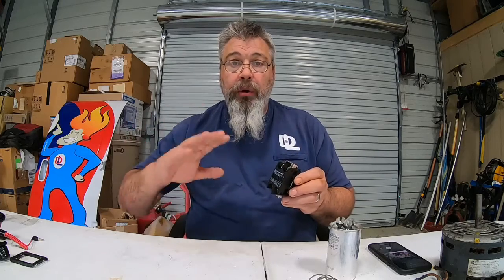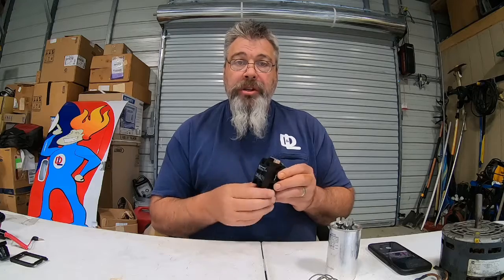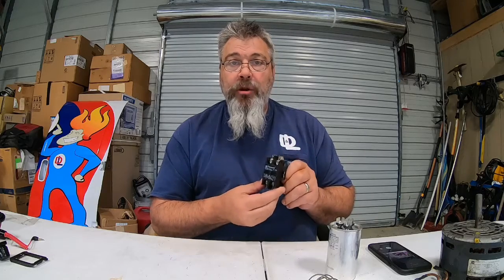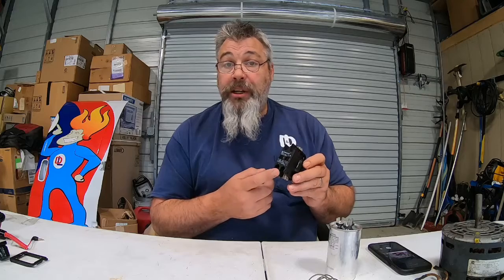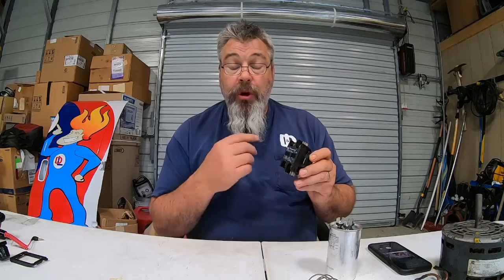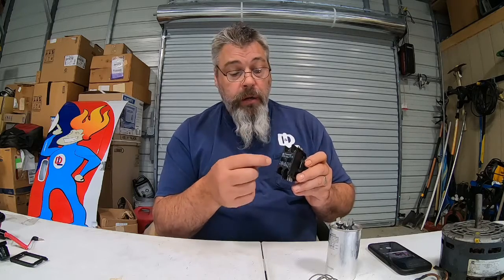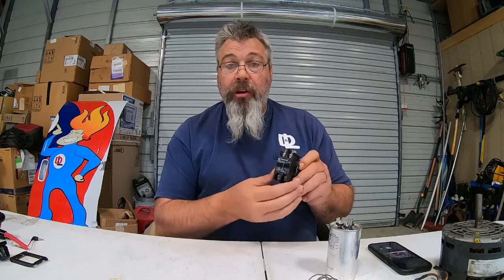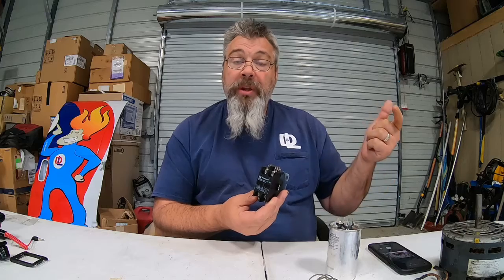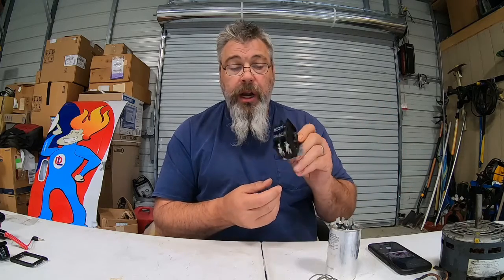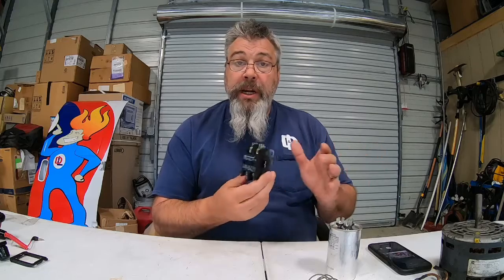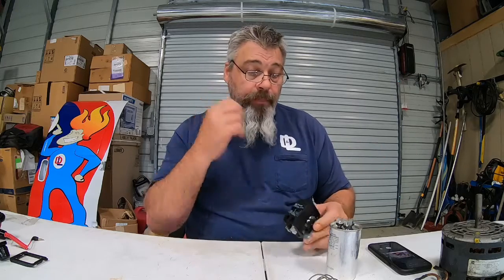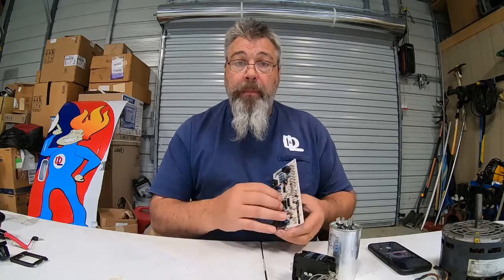Now your thermostat is basically your control board. That's inside. We'll talk about that in a different video, but I wanted to go over today the components internally inside your heat pump. So a contactor acts like a light switch. When you don't have any call, the light switch is off. When you have a call, the light switch goes on, energizes this, pulls the contactor in, and allows high voltage to come out of here, go and feed your fan motor, and start your compressor. Okay, so a contactor is another component that's in your heat pump or AC unit. It's going to be in both of them. Okay. Next component I want to talk about is a control board.